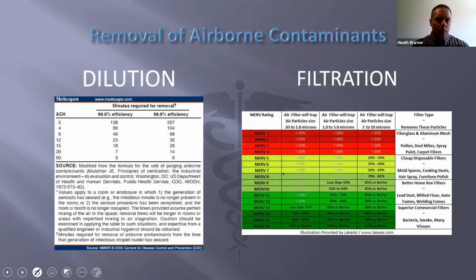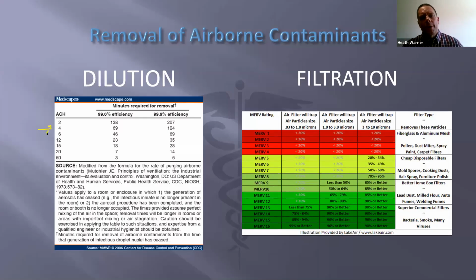Sounds well and good. When you're talking about the removal of those airborne contaminants, there are basically two sides to the coin: dilution and filtration. Dilution's pretty self-explanatory, and I'm sure most of us here know the golden rule for HVAC design for most safe buildings, why they keep doing that, I don't know, is 4 air changes per hour, somewhere between 4 and 5. And the real reason behind that, the magic starts happening, is that in order to clean out 99% of the particulates that are in there, it takes about 69, 70 minutes at 4 air changes an hour. That's why if you can push it to 5, continually cycling that air will keep the air much cleaner and effectively move the air out every hour.